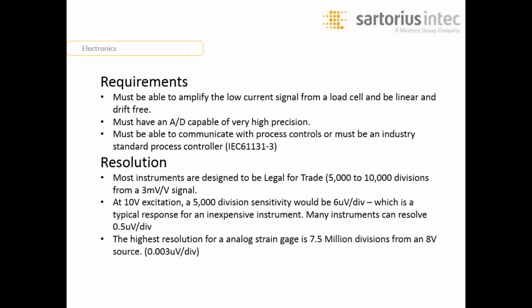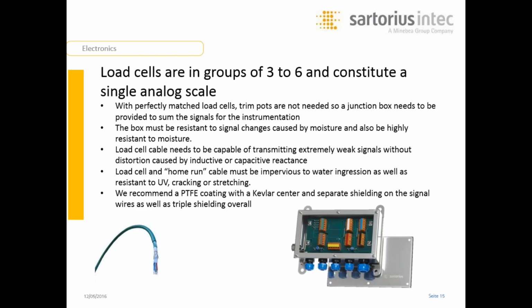Resolution. Most instruments are designed to be legal for trade, 5,000 to 10,000 divisions from a 3 millivolt per volt signal. At 10 volts excitation, a 5,000 division sensitivity would be 6 microvolts per division, which is typical response for an inexpensive instrument. Many instruments can resolve half a microvolt per division. The highest resolution for an analog strain gauge is 7.5 million divisions from an 8-volt source, or 0.003 microvolts per division.